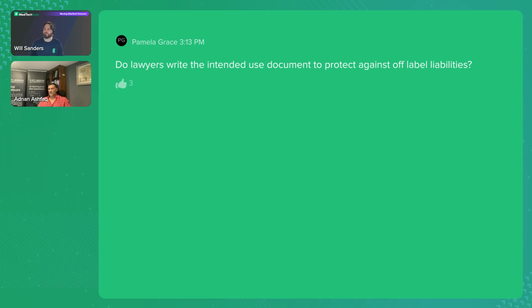You talk about off-label liabilities, but the off-label liabilities also have to come back to your risk management, because your risk management will look at any risks which are off-label. We have to make sure that, when we look at risk management, it is within the boundaries of reasonably foreseeable misuse. Those are the key terms, because off-label can sometimes go way out there, which is not reasonable and not foreseeable. That's why anything we look at has to be reasonably foreseeable.